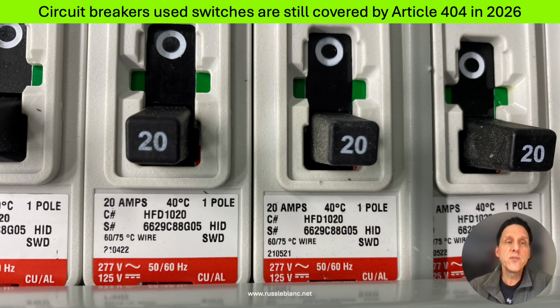And circuit breakers used as switches will still be covered by 404 in 2026. Now, if you look at the circuit breakers, in the white portion, the white and black lettering, you'll see some markings there. And one of the markings you'll see is SWD. So these are switch rated or switch duty rated. So you can use these to turn on and off lights every day as if it was a wall switch. And that's how I've seen them used for a store, for example.